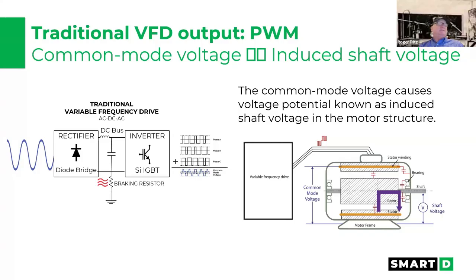So you'll see there's multiple companies out there, carbon brush companies, and Aegis grounding rings that are out there, needed to basically try to eliminate this common mode voltage. The problem is you've got to read the fine print, where they say those brushes and rubbing points have to be cleaned every year, or it'll start building a film on them, and then it'll stop working, and it'll still take your bearings out. So then they went to ceramic balls in the bearing, which helped. But all of these things, in my opinion, are just band-aids. They're putting band-aids on the real problem, which is the VFD frequency of the IGBT.